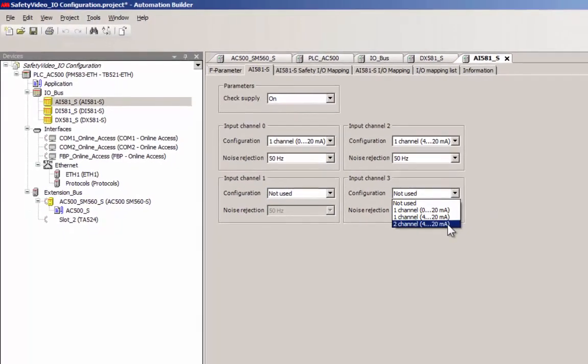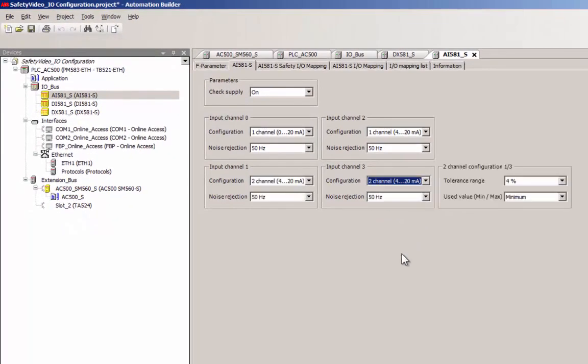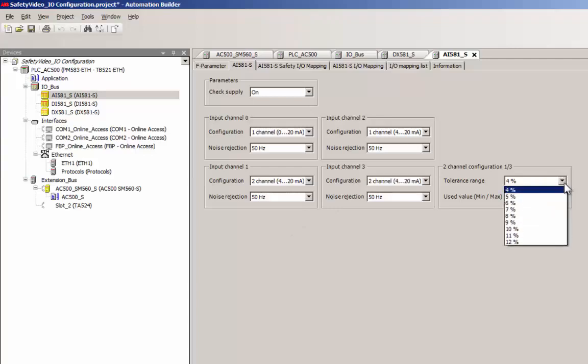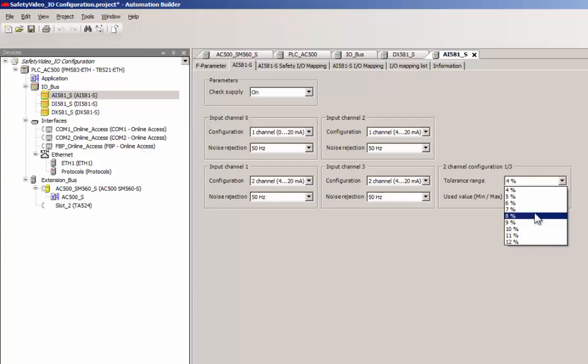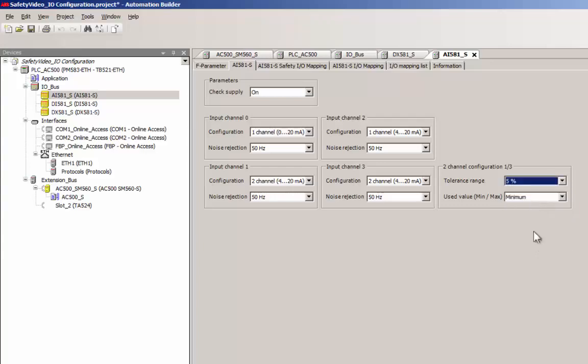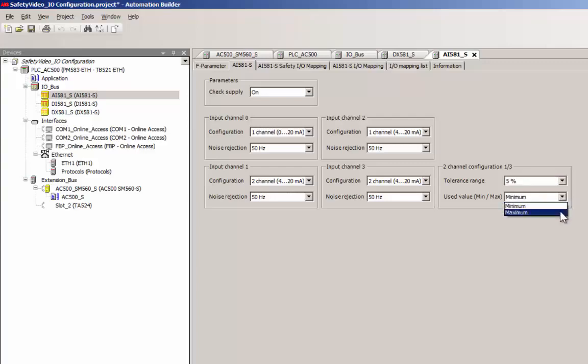Channels can also be configured as two channel type for a signal range of 4 to 20 milliampere. In a two channel type input, an appropriate tolerance value should be set to avoid frequent channel passivation. User could also choose whether the minimum or maximum of these two values should be used in the safety CPU.